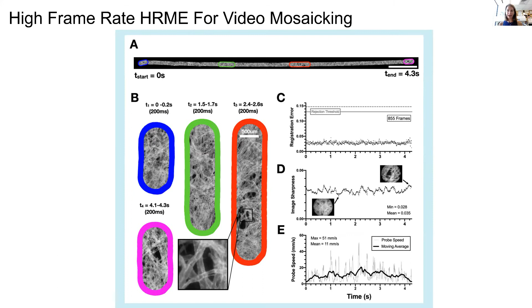We call it video mosaicing, and we started by testing it on lens paper that had been colored with a fluorescent highlighter. Here is a mosaic that is built over the course of 4 seconds from one end of the lens paper to the other end. If we zoom in here, we have really nice resolution of the fibers in the lens paper. We track our registration error and defined a rejection threshold. In this example, where we collected nearly 900 frames, all of them passed that quality control metric. And you can see we can translate the probe at speeds ranging from 11 to 50 millimeters a second across the lens paper. So the question is, does that work in tissue?